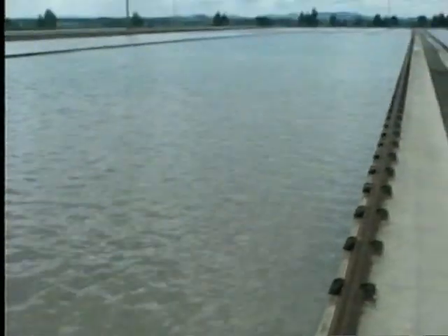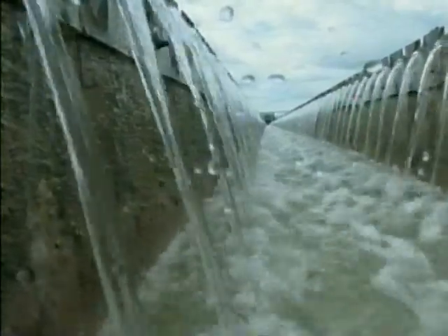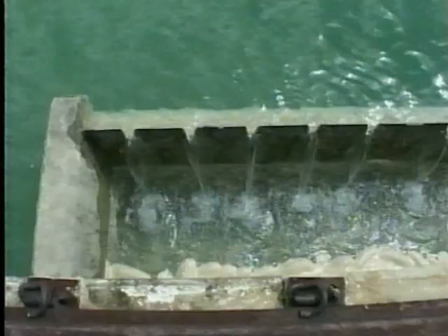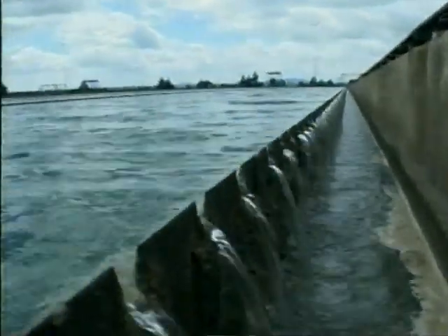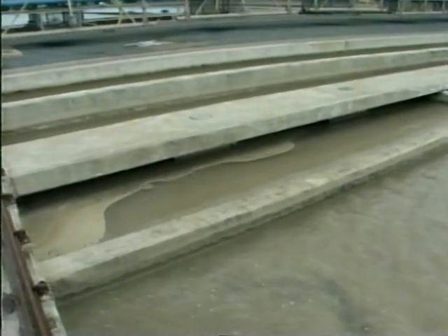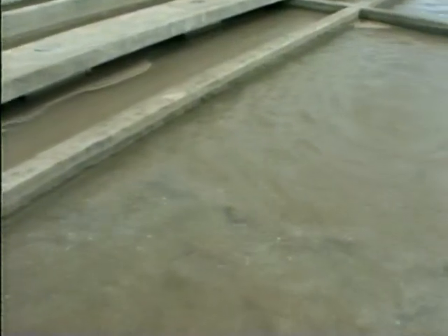Sedimentation is the oldest known method of water purification and has been employed extensively for thousands of years. Although it is a natural phenomenon, it is aided by the addition of chemical coagulants to produce flocs, which are allowed to settle in specially designed tanks, which are also engineered to remove sludge. Rand Water uses horizontal flow tanks with retention times of 4 hours and produces clear water at the outlet weirs. Between 95% and 97% of the suspended particles are removed during sedimentation.